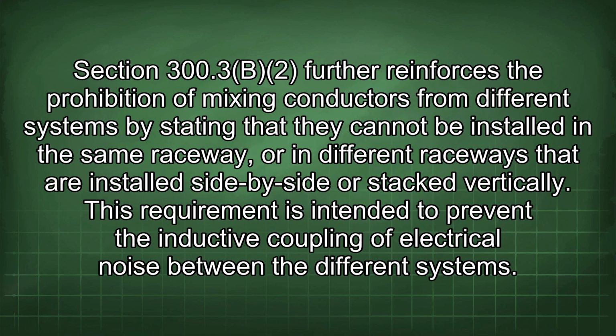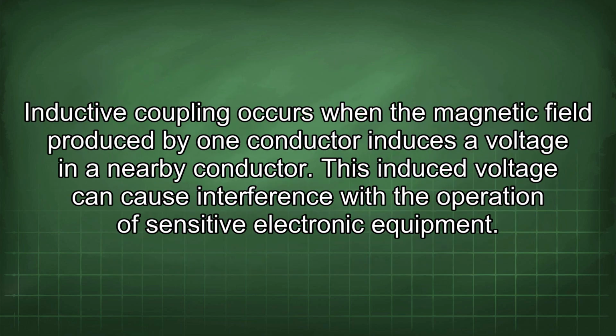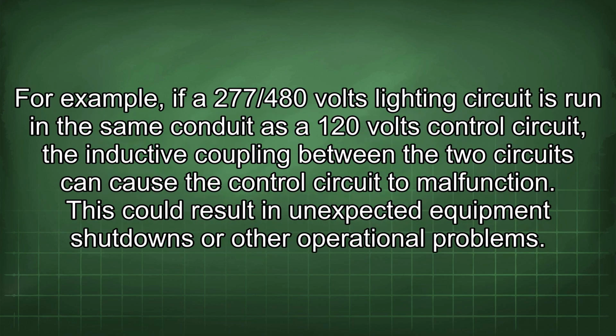Section 300.3(B)(2) further reinforces the prohibition of mixing conductors from different systems by stating that they cannot be installed in the same raceway or in different raceways that are installed side by side or stacked vertically. This requirement is intended to prevent the inductive coupling of electrical noise between the different systems. Inductive coupling occurs when the magnetic field produced by one conductor induces a voltage in a nearby conductor. This induced voltage can cause interference with the operation of sensitive electronic equipment. For example, if a 277/480 volt lighting circuit is run in the same conduit as a 120 volt control circuit, the inductive coupling between the two circuits can cause the control circuit to malfunction. This could result in unexpected equipment shutdowns or other operational problems.